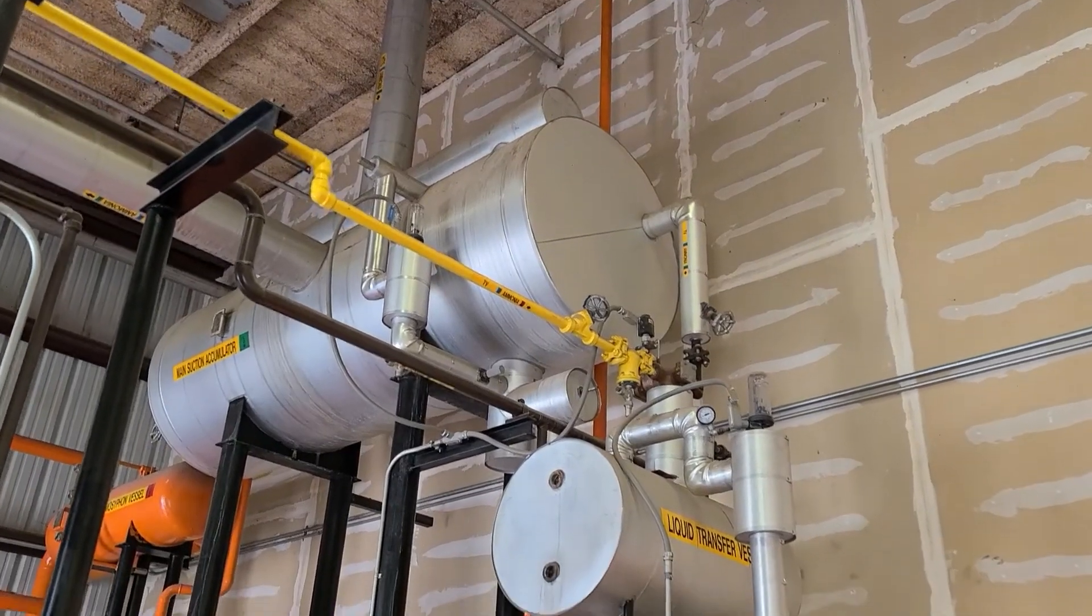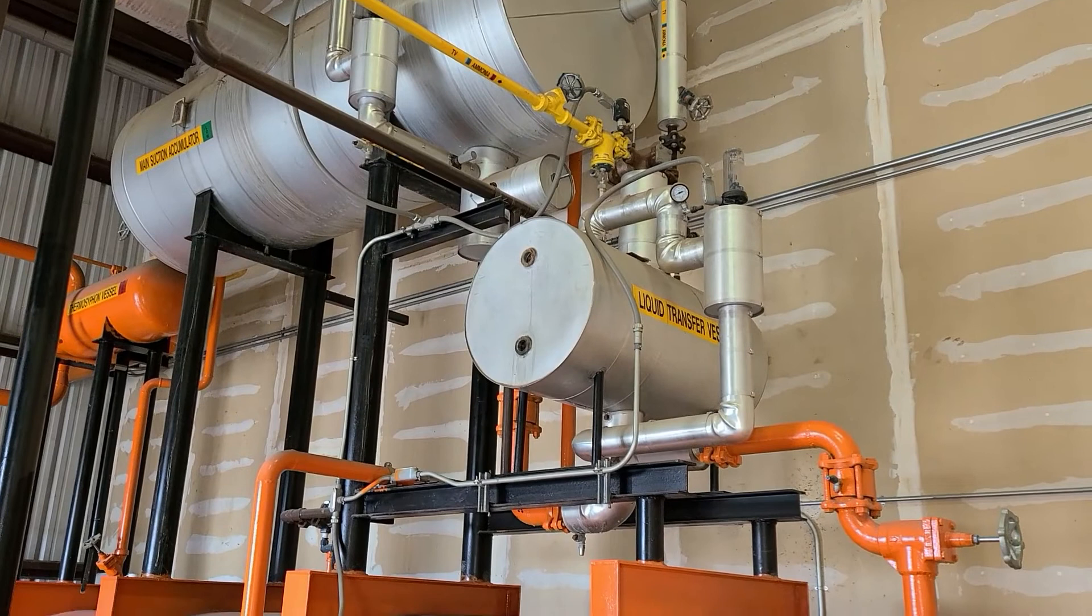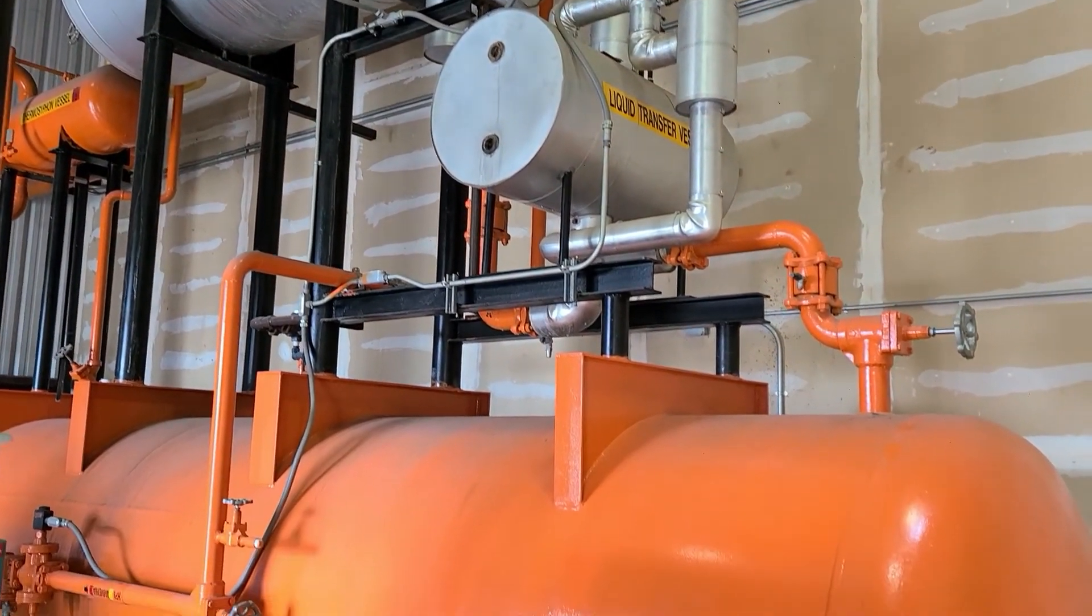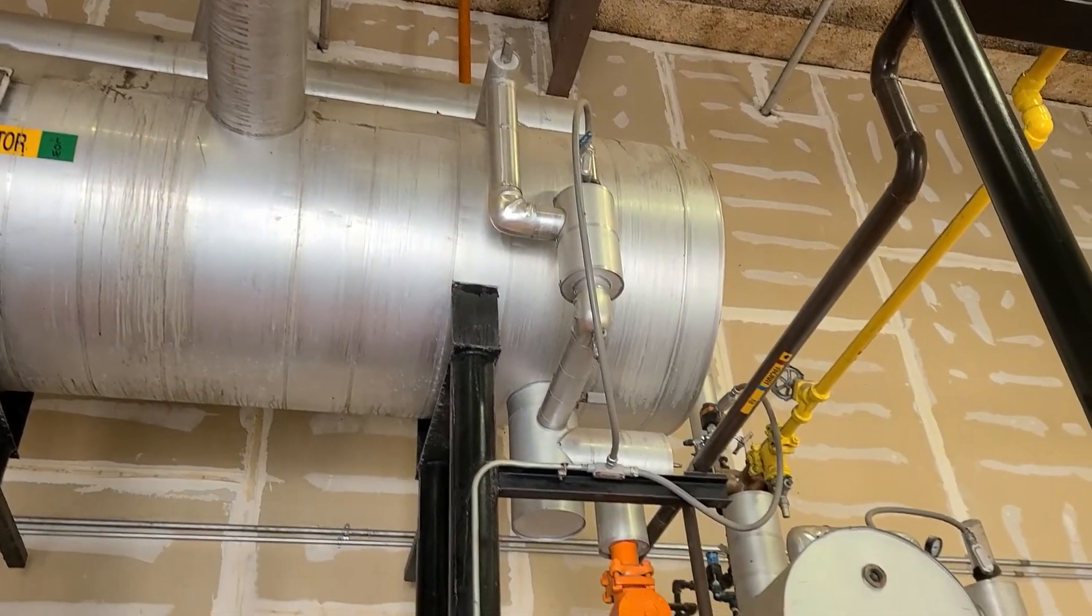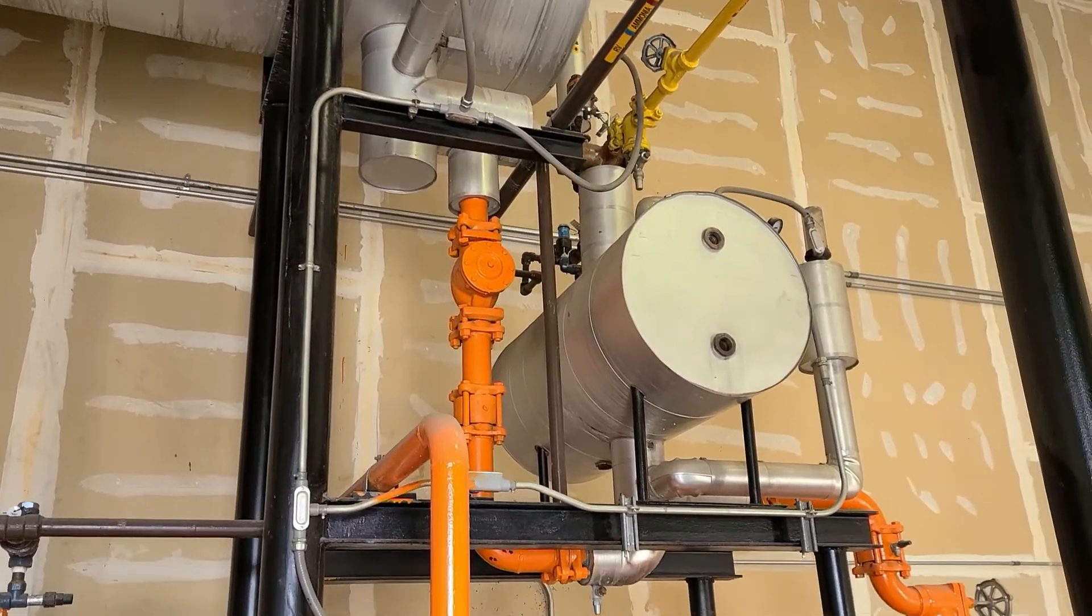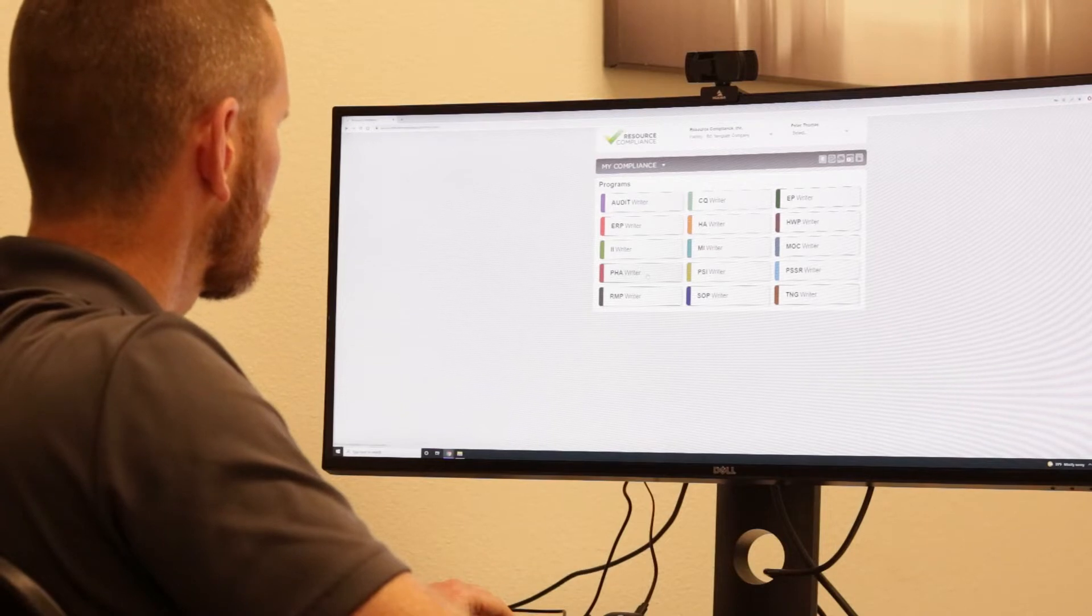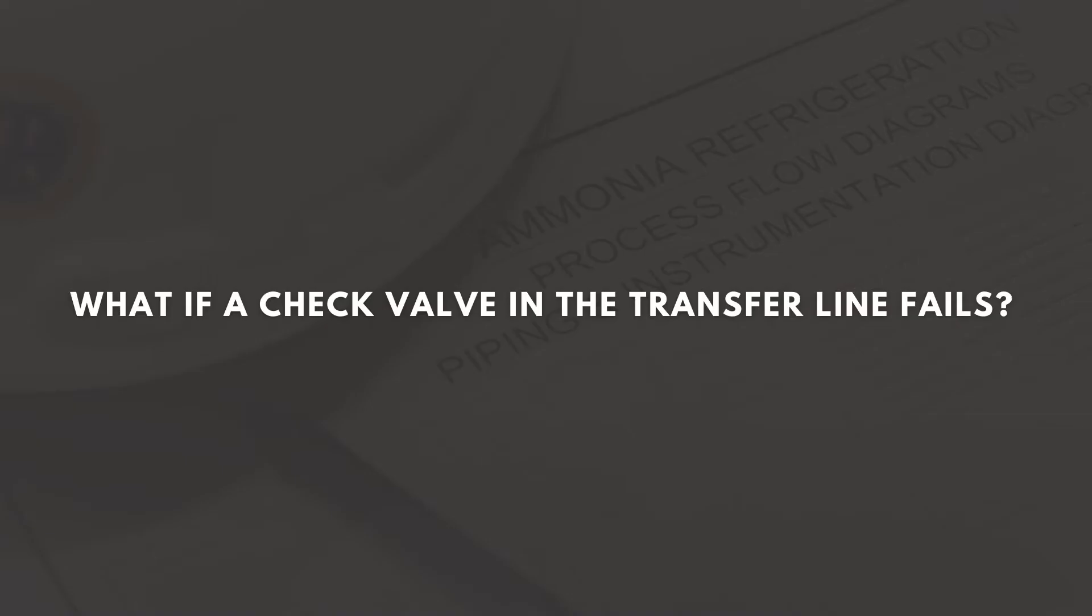Often, P&IDs will assist in visualizing and analyzing the scenarios being examined. For example, many flooded refrigeration systems are configured with a liquid transfer vessel that is designed to move unwanted liquid on the low side of the system back to the high-pressure receiver. The piping that connects the transfer vessel to the high-pressure receiver and suction accumulator must have a check valve to prevent reverse flow. A common PHA question for this component is, what if the check valve in the transfer line fails, which could occur in the following scenario.